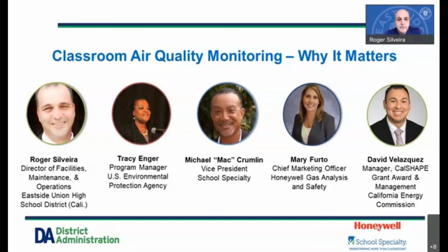Again, my name is Roger Silvera. I'm the Director of Maintenance, Facilities, and Operations for Eastside Union High School District. I started with Eastside back in 2017, and one of my first tasks was to triage a building, a cluster of classrooms that had an odor problem, and several teachers complaining about symptoms, headaches, fatigue, nausea from being inside those classrooms. What I found was the ventilation system had been disabled, and that building had no ventilation. And so some of the teachers were suffering from those symptoms.